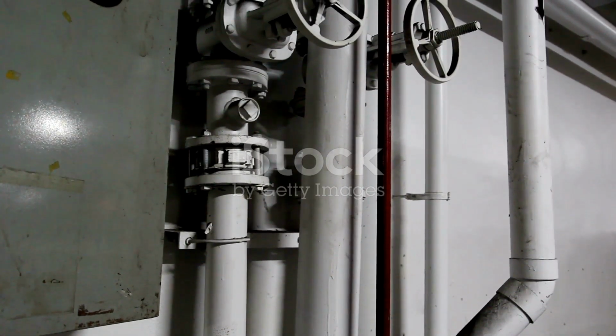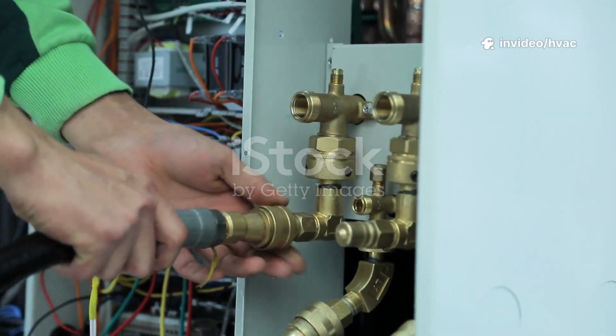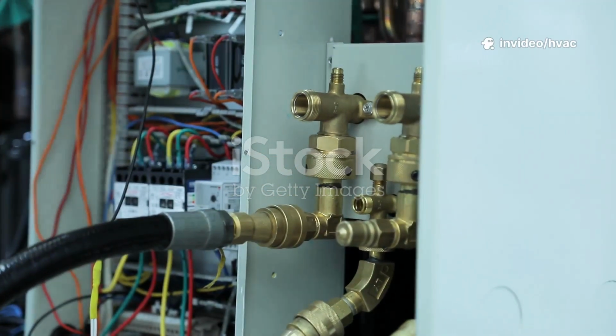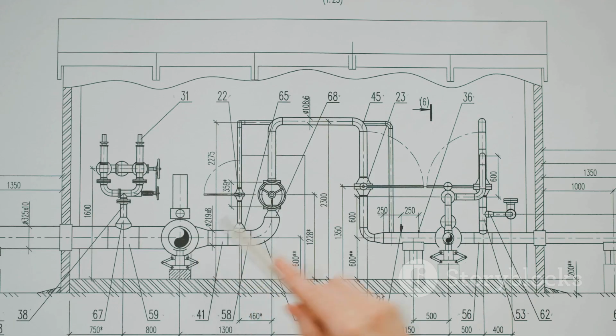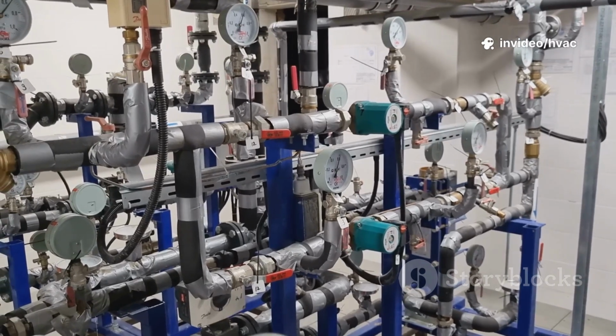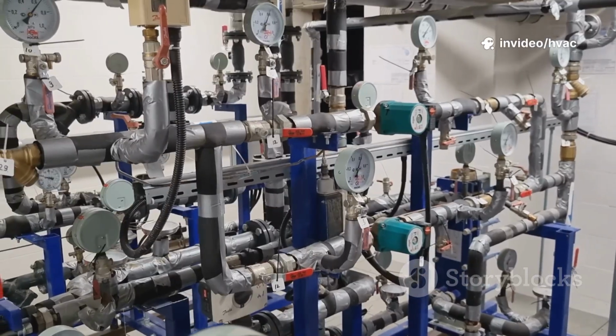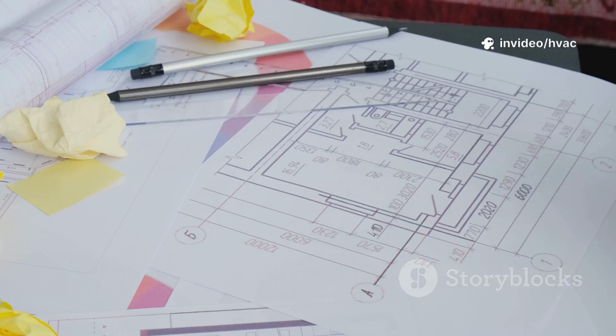The importance of PICVs in modern HVAC systems cannot be overstated, especially when it comes to system balancing. Traditionally, balancing a hydronic system was a very time-consuming and difficult process. Technicians would have to go to every single valve in the building and manually adjust it. This process, known as static balancing, was often iterative, meaning that adjusting one valve would affect all the others. This required multiple passes through the entire building to get the flows just right. PICVs eliminate this entire process. Because each valve automatically regulates the flow to its terminal unit, the system is dynamically balanced from the moment it is turned on. This is a huge advantage for any new construction or renovation project.